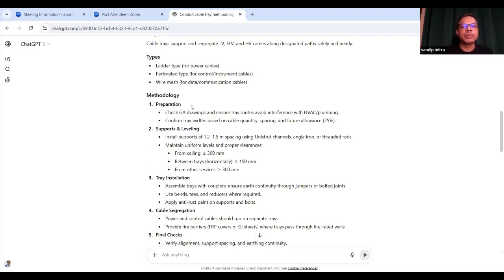For the methodology preparation, check the GA drawing, and ensure tray routes avoid interference with HVAC and plumbing. Confirm tray width based on cable quantity, spacing, and future allowance. So all things you need to consider. In future also you need to provide some space, because the power requirement may increase. So you need to provide the space in the cable tray.